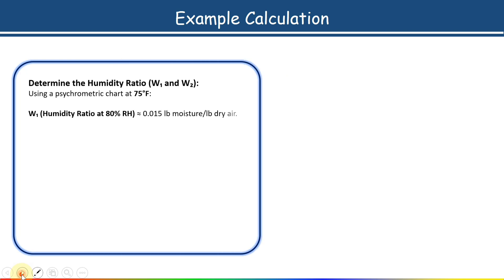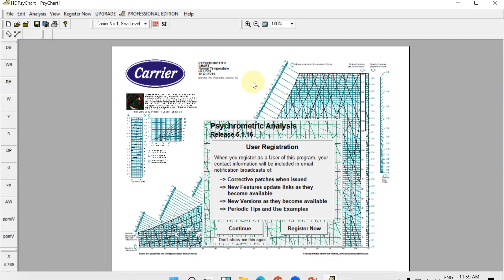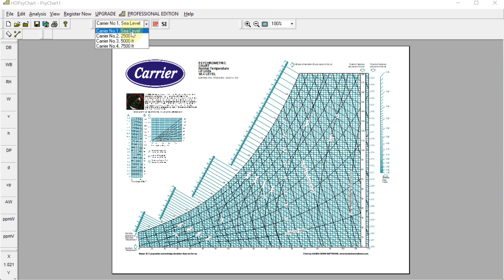Next, calculate the humidity ratio value using psychrometric software. Based on the supply temperature of 75°F and the initial relative humidity of 80%, from the psychrometric chart or software we get a humidity ratio W1 of 0.015 pounds of moisture per pound of dry air. To use the software, open it, hit Continue, and select the sea level — if your sea level is less than 2,500 feet, select the first option. The sea level value can be found from the ASHRAE handbook outside design data.